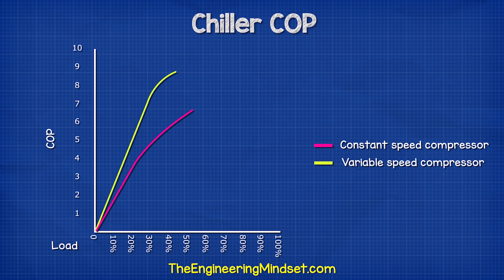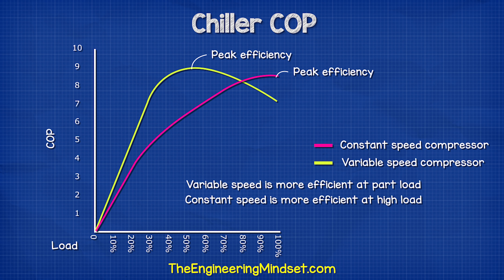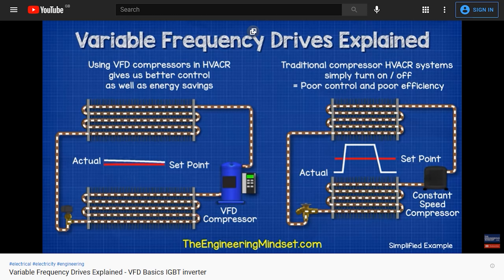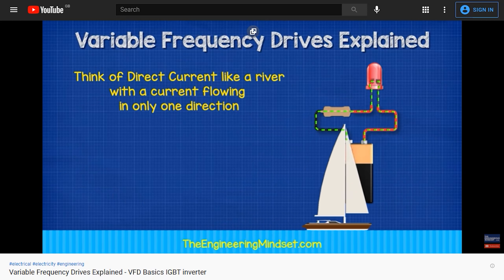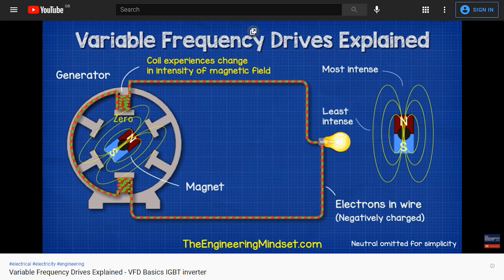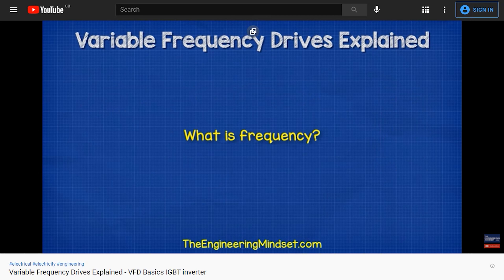We can see from these charts that the variable speed compressors generally do not perform efficiently at full load because of the inverter losses. So at full load, it is usually more efficient to run a constant speed compressor chiller. You can also learn how variable frequency drives work in detail in our previous video — I'll leave a link in the video description below.